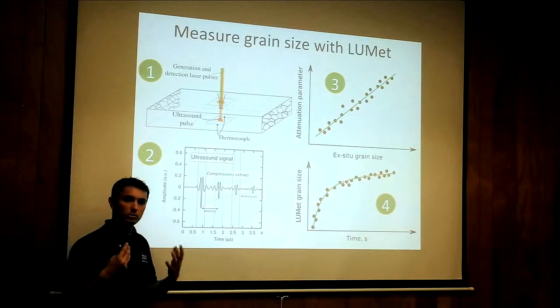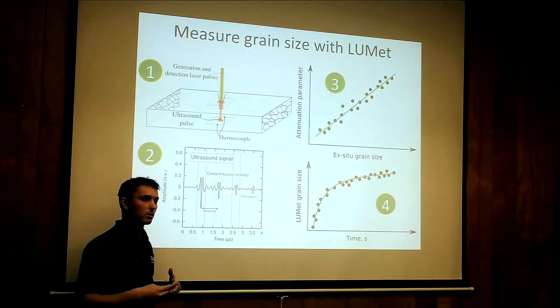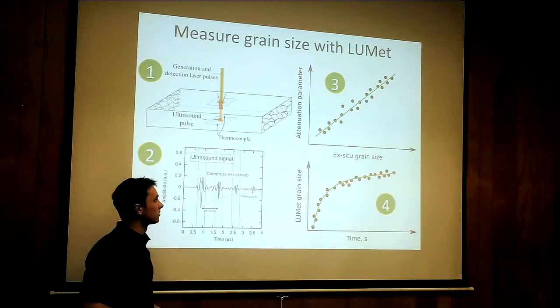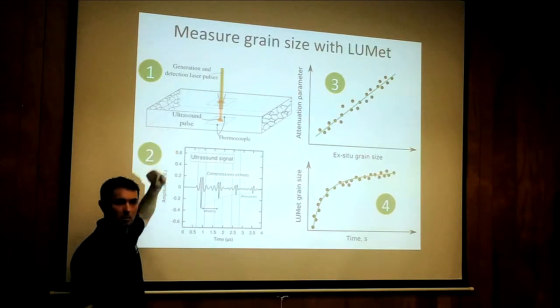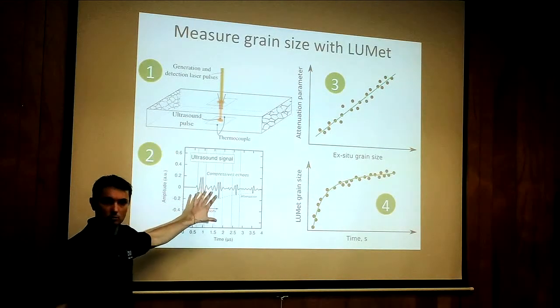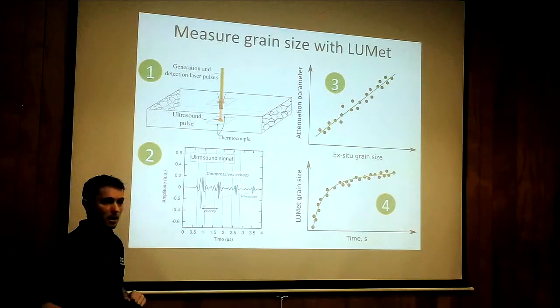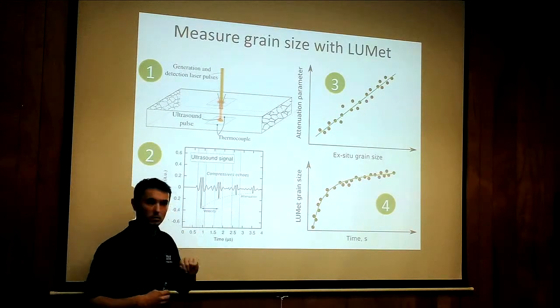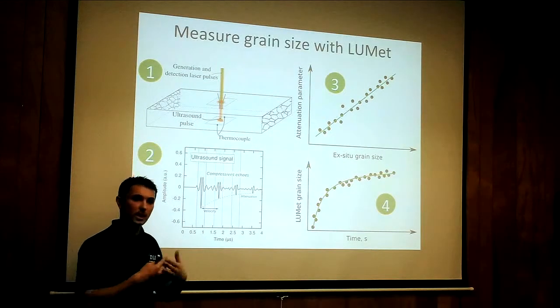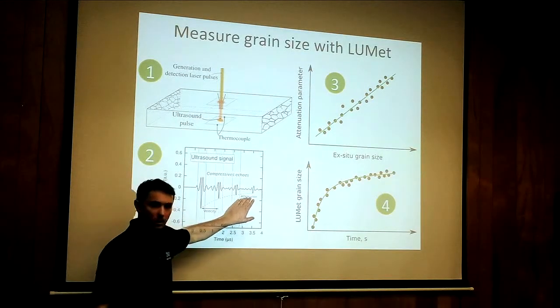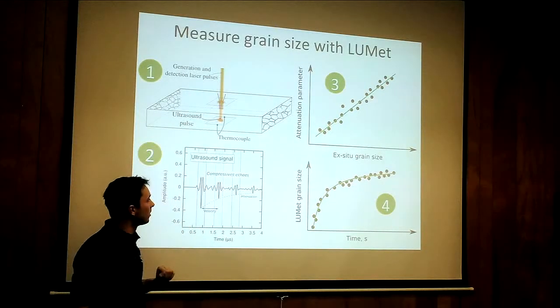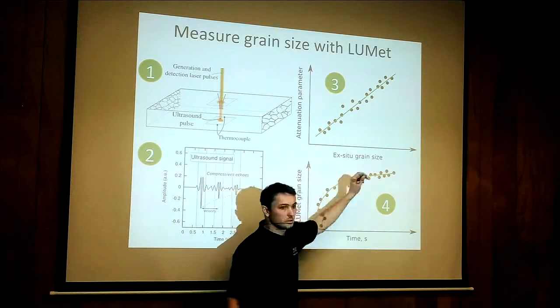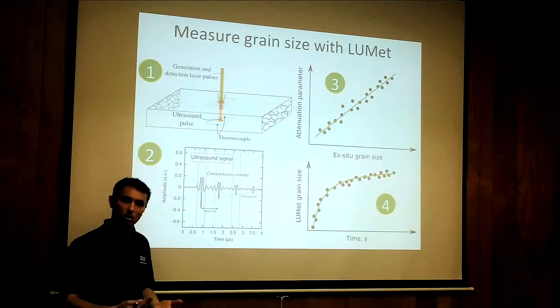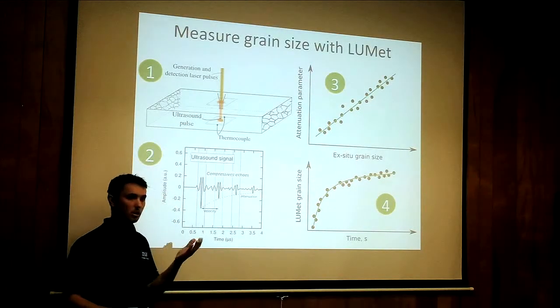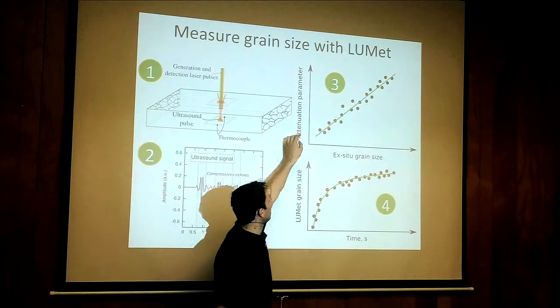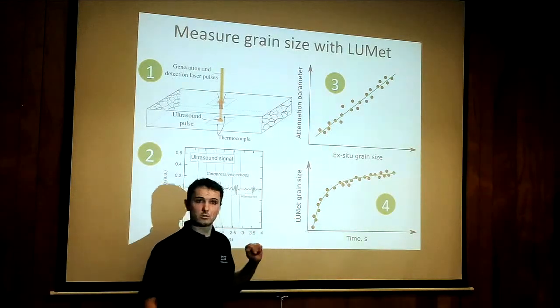So now I'd like to show the basic principle of grain size measurement with Lumet. Of course, you have to do the experiment in the Gleeble machine. You capture this raw signal, which is the second step. And then the important thing, once you have measured the attenuation, is to build what we call the calibration. Using this attenuation value that you have measured, you can correlate it with a grain size that you can measure ex situ, using optical metallography in a sample in which you know the grain size. You can relate this attenuation value to a grain size that you know.